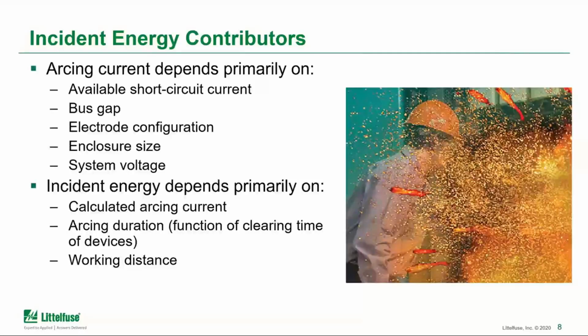The system voltage as well obviously does have an impact. Sometimes it could be assumed that a higher voltage is a higher risk, but that's not always the case. Low voltage systems do have higher fault current levels, so that could contribute to higher energy ratings. But of course, the higher current values could also engage overcurrent protection at different ranges. So that can also have an effect on the protection.